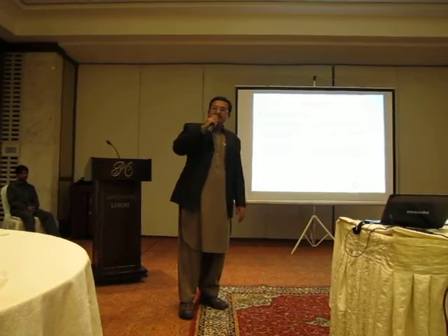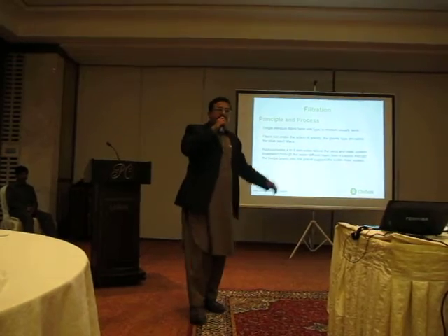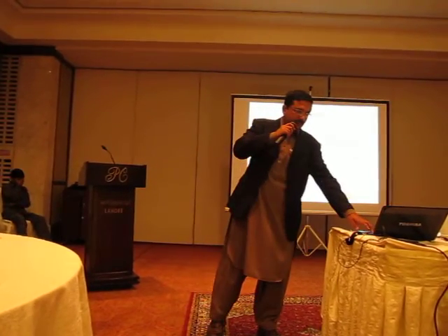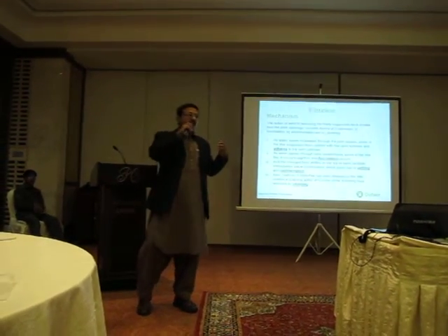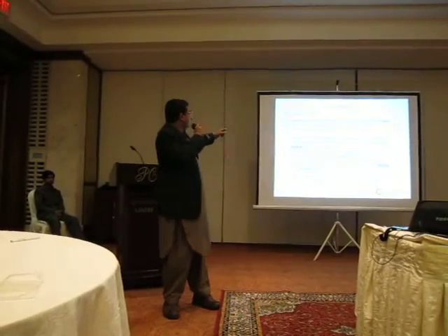In single medium filtration we have a sand bed, and it runs under the action of gravity. Water stands 3 to 4 feet above the sand bed and passes through the sand bed and through the gravel to the underdrain system and is collected. So one of you will be thinking about how a sand bed can clean water. There are 4 mechanisms taking place: adhesion, flocculation, sedimentation, and straining.